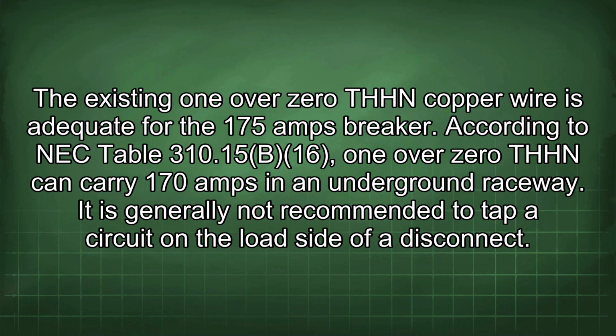The existing 1/0 THHN copper wire is adequate for the 175 amps breaker. According to NEC Table 310.15(B)(16), 1/0 THHN can carry 170 amps in an underground raceway.